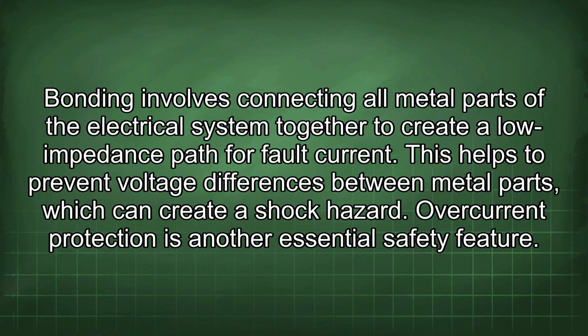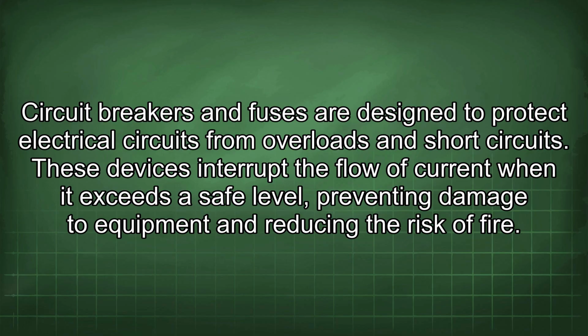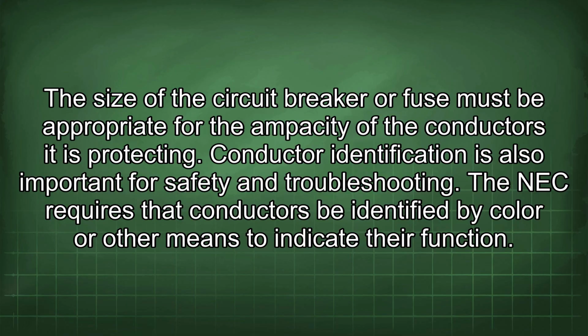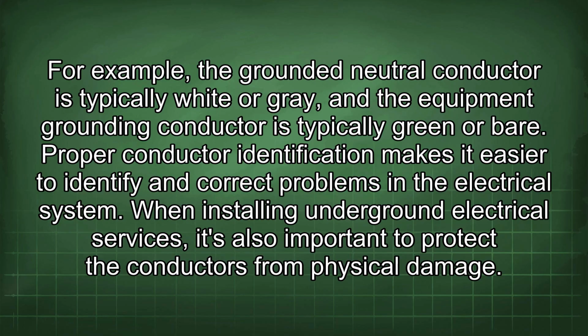Overcurrent protection is another essential safety feature. Circuit breakers and fuses are designed to protect electrical circuits from overloads and short circuits. These devices interrupt the flow of current when it exceeds a safe level, preventing damage to equipment and reducing the risk of fire. The size of the circuit breaker or fuse must be appropriate for the ampacity of the conductors it is protecting. Conductor identification is also important for safety and troubleshooting. The NEC requires that conductors be identified by color or other means to indicate their function. For example, the grounded neutral conductor is typically white or gray, and the equipment grounding conductor is typically green or bare. Proper conductor identification makes it easier to identify and correct problems in the electrical system.